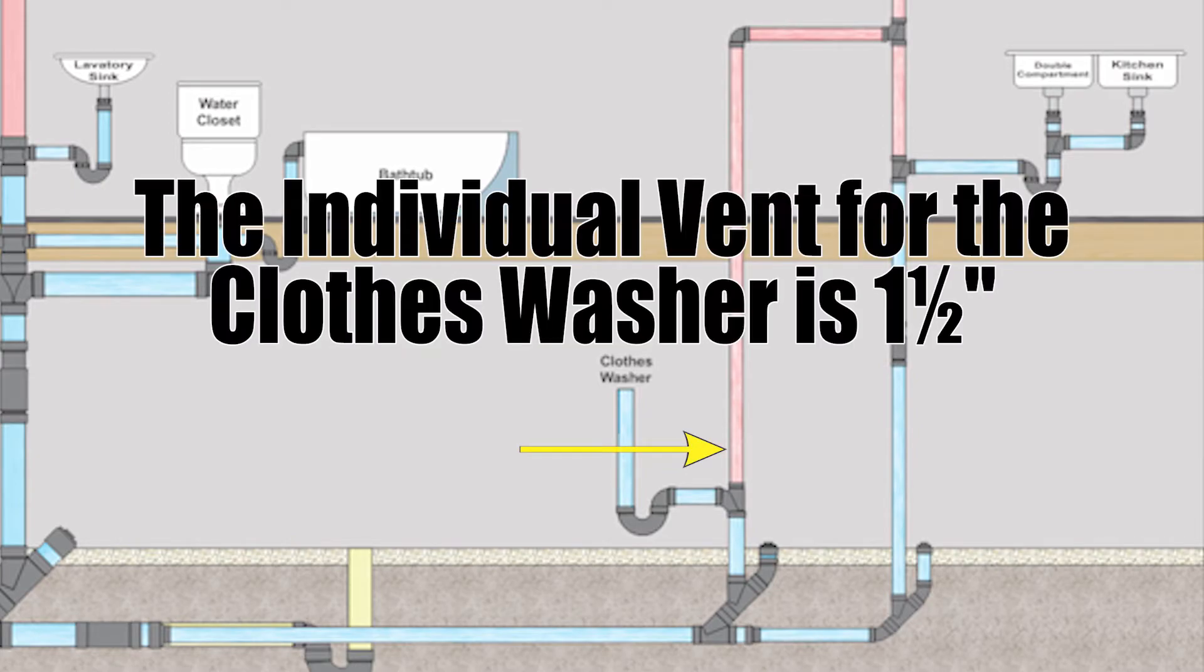Now that clause about sizing individual vents said something about not taking length into consideration. For most vents you actually have to measure the vent in meters and then apply that to a table. But for individual vents and for dual vents you don't need to measure it. So we don't have a developed length for it. We don't care. That could be a hundred meters long. It could be five meters long. It doesn't matter. It's inch and a half. It's done.